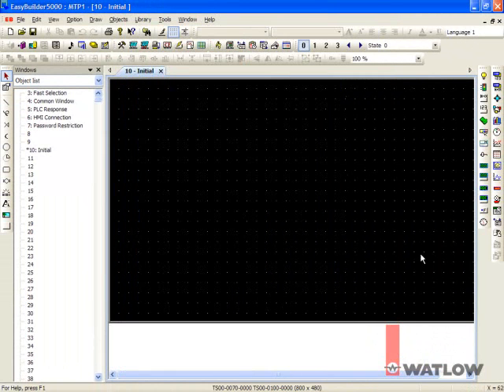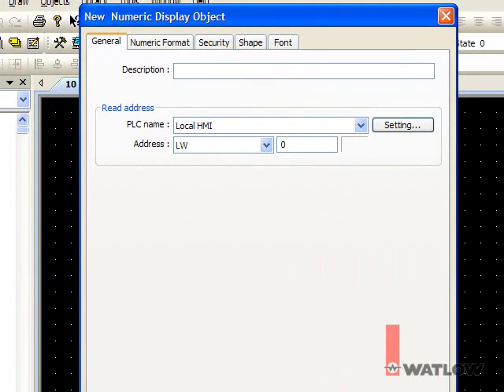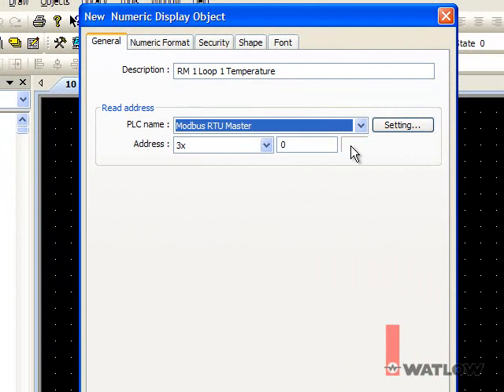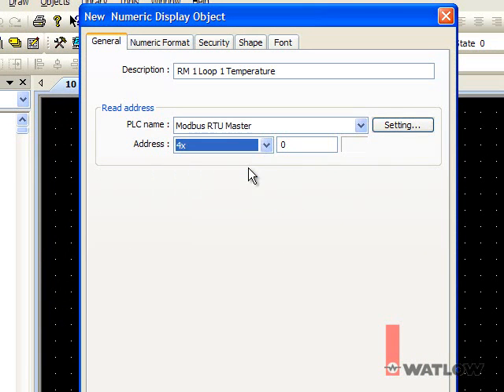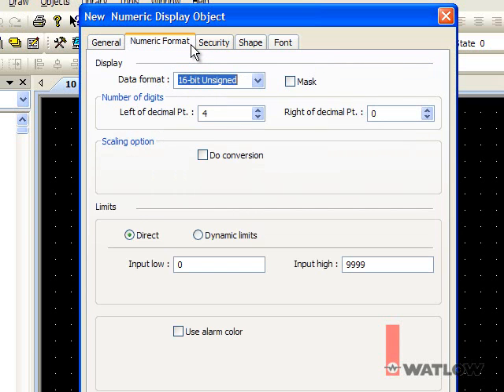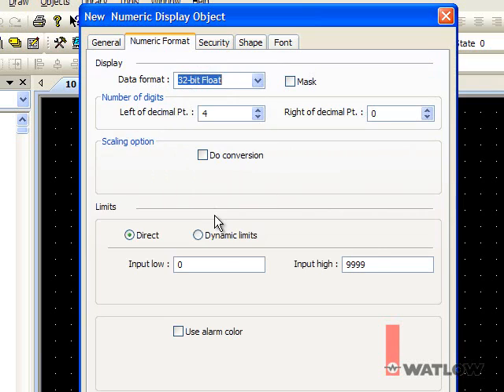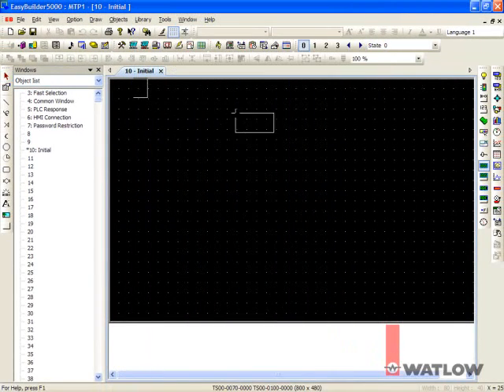Now we can start creating an interface. Add a numeric display for the first process value in the control module with address 1. Enter a description. For PLC name, choose Modbus RTU Master. For address, choose 4X and enter 361. You must add a 1 to the address indicated in the EZZone manuals. On the Numeric Format tab for Data Format, choose 32-bit Float. Click OK and place the field.